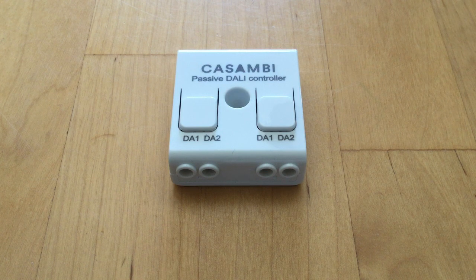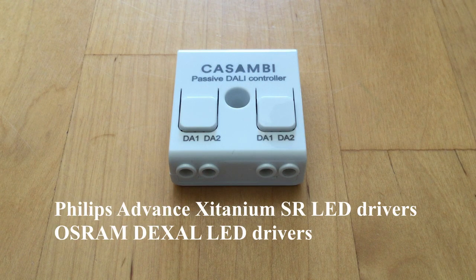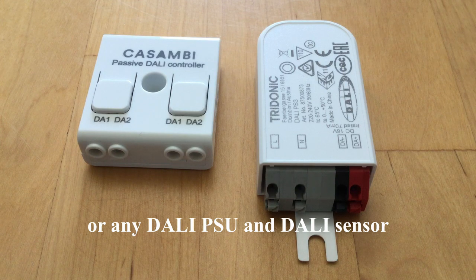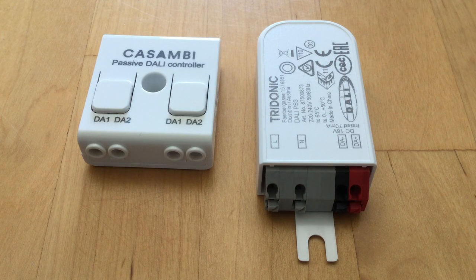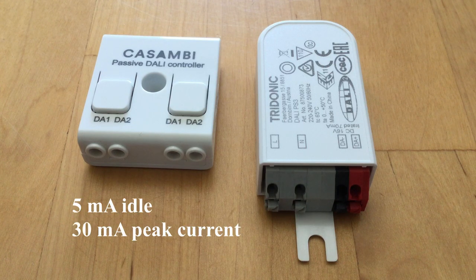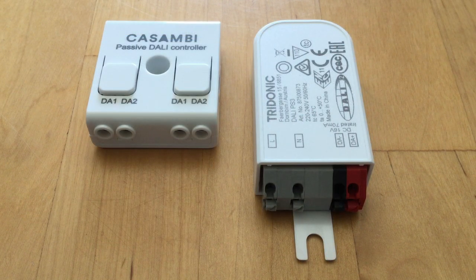This is the CBU-DCS. It's pretty much a passive version of the CBU-ASD which you've just seen, so it requires its own power supply. Casambi originally designed this to be used with the Philips Advance Xitanium SR LED drivers, and also any Osram drivers which use the DEXAL technology. It can, however, also be powered by a DALI power supply. The device itself requires 5 milliamps when powered on and idle, and can take up to 30 milliamps at peak current. It's also possible to connect a DALI sensor to this device, which I'll show in the next example.